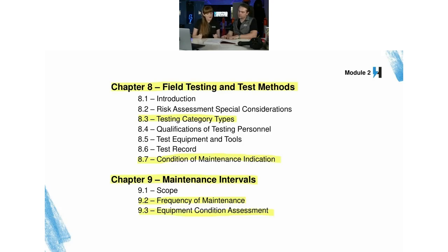Yep. So also highlighted is what's called conditions of maintenance. So you have serviceable, limited service, and non-serviceable. Serviceable just means equipment that passes all tests and is electrically and mechanically sound shall be designated as serviceable. Limited service is equipment that has problems that are not detrimental to the protective operation or design characteristics of the equipment shall be designated as limited service. Yep. And then finally, non-serviceable is equipment that has a problem that is detrimental to the proper electrical or mechanical operation of the equipment shall be designated as non-serviceable. Right. So you have to make sure you classify your equipment in certain ways in order to determine how often you need to do maintenance and whether or not you're even able to do that maintenance, or if it just needs to get replaced, essentially.